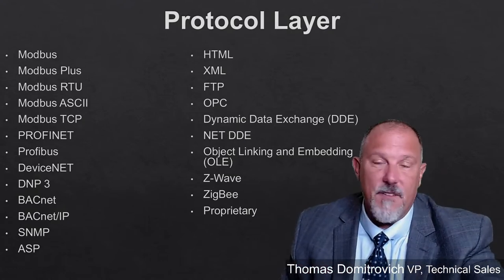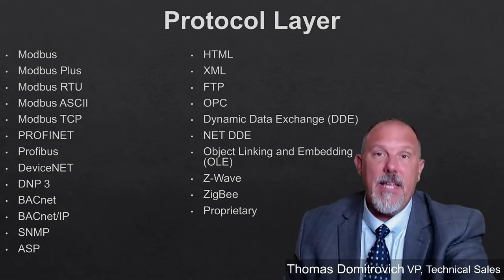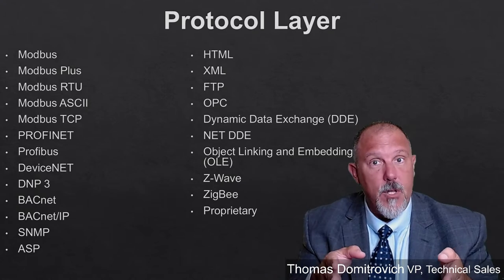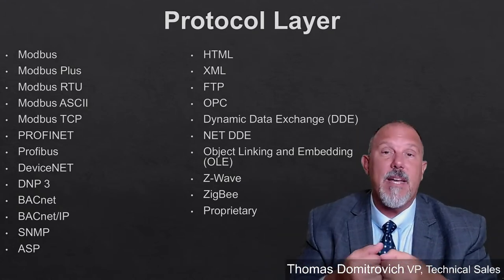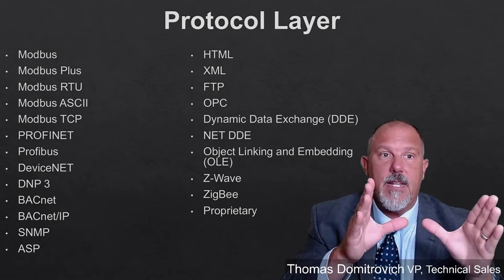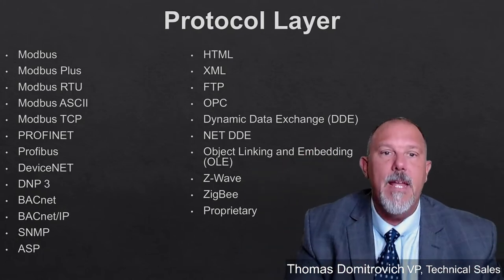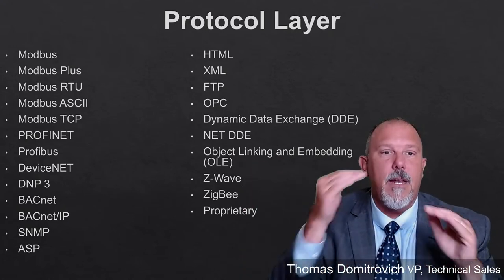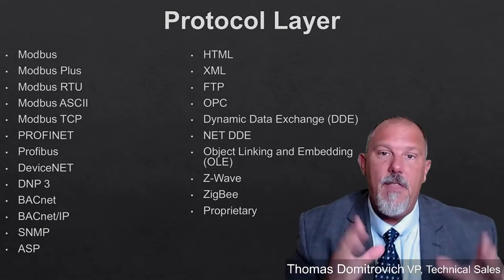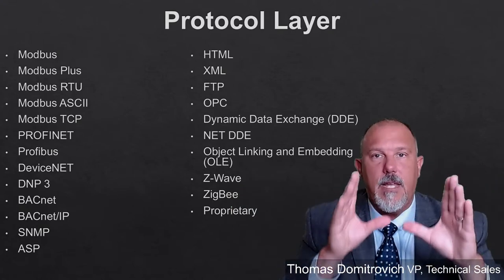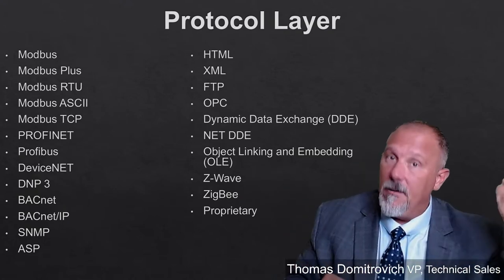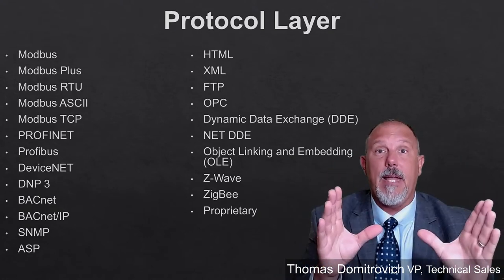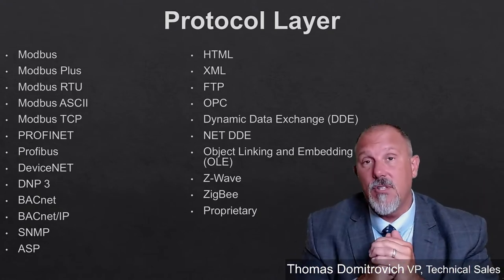One that speaks DeviceNet, one that speaks Modbus TCP, and one that speaks Modbus RTU, and treat each of those separately from a physical layer back. Maybe I have a gateway, a device that has a card that accepts Modbus RTU, another card with an Ethernet port that accepts Modbus TCP, and another port that accepts DeviceNet. And then in this box, I map all of my data and output it maybe onto an Ethernet LAN, or maybe I'm going straight to a display, displaying the data from each of those networks.